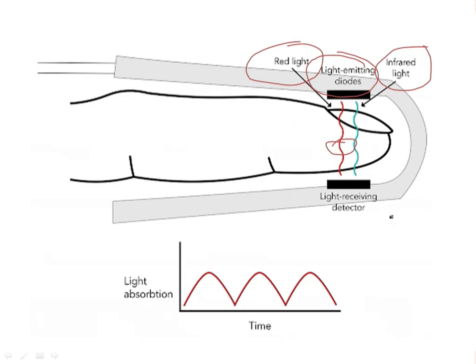So the red light from the light emitting diode to the light receiving detector, or photodetector, will be associated with detecting deoxygenated hemoglobin. By the same way, the infrared light, with wavelength 940 nanometers, will be absorbed by the oxygenated hemoglobin.